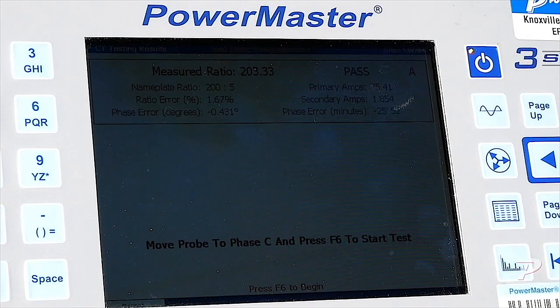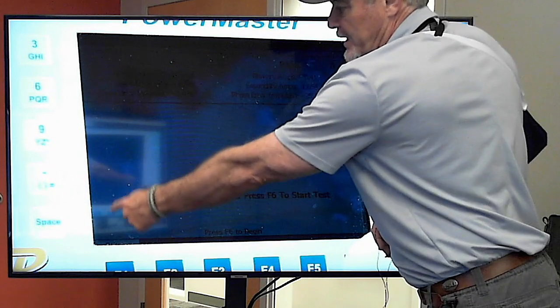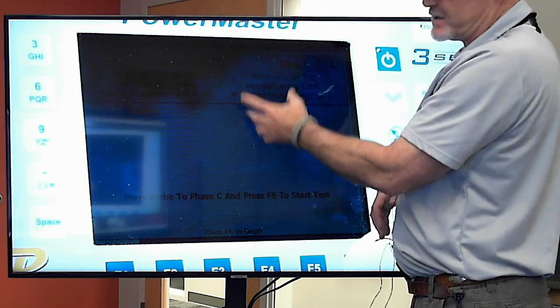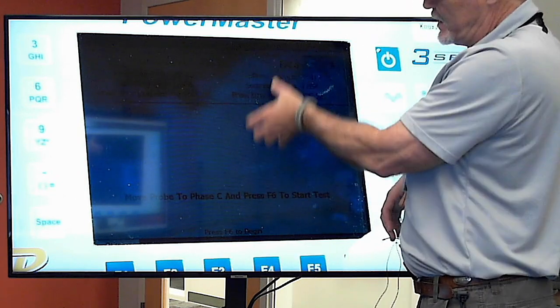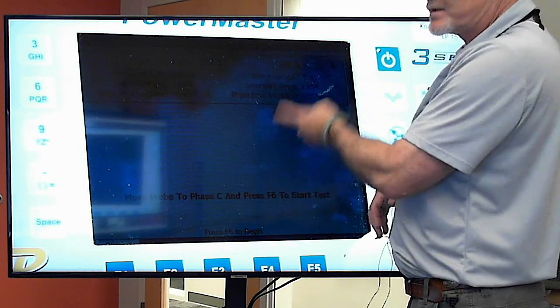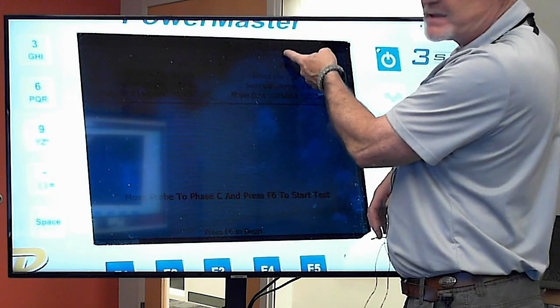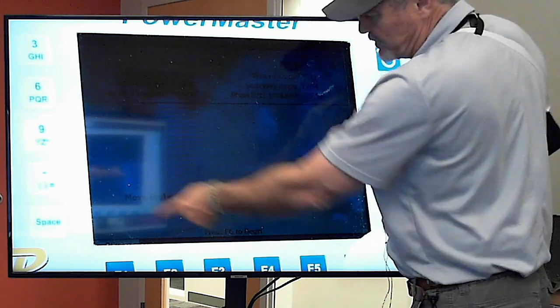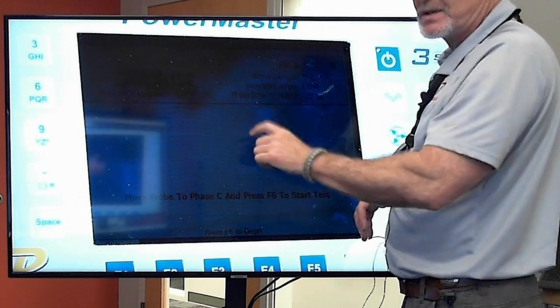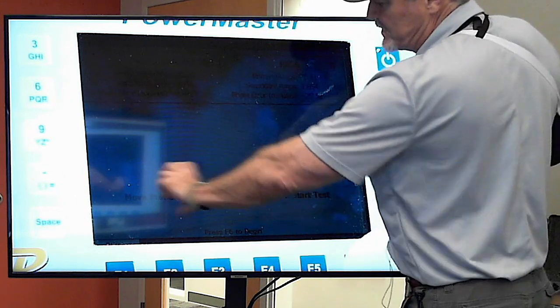Move probe to phase C. Remember what we've talked about before on the retest. It ended up right with a gold box around there at the bottom. If you've been testing all three phases, same thing, it ends up on C phase. If you go A, B, then C, it ends up with the gold box around C at the end, and you can just move that. So you can move the gold box if you need to move it up and retest just that phase. And then it was already on C phase, so we just hit retest. You could retest all of them or retest just the one with the gold box. So we just retested C phase because we'd already tested A.